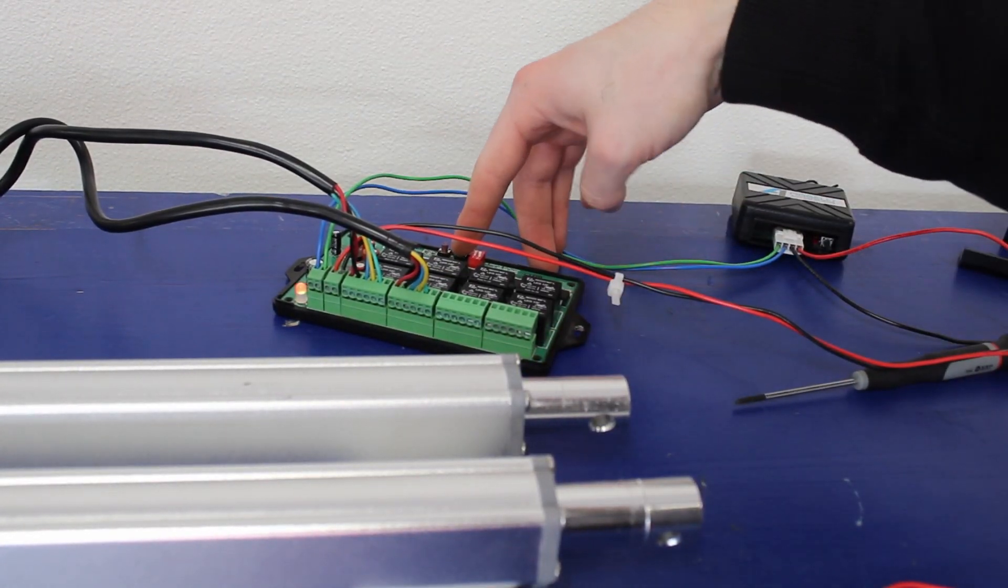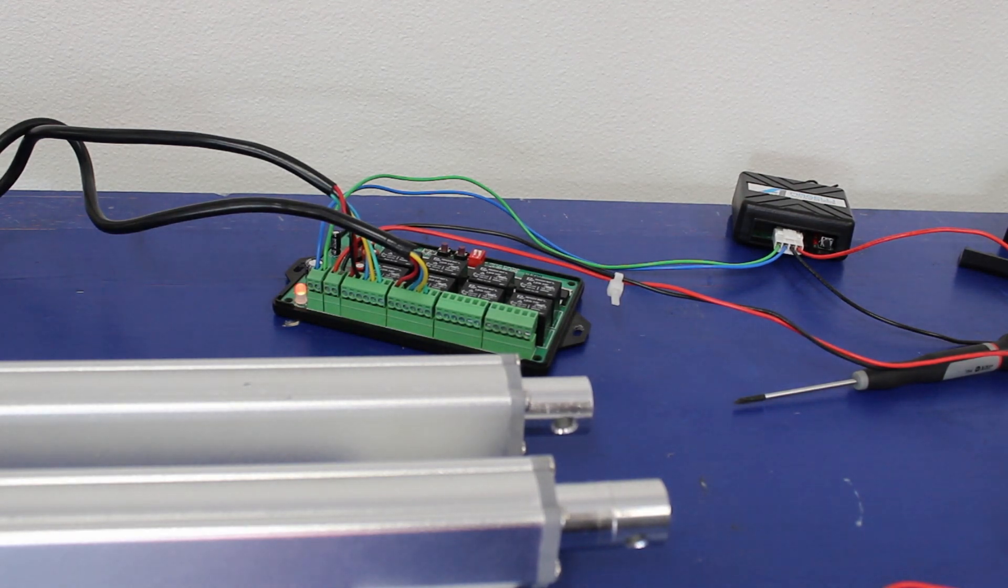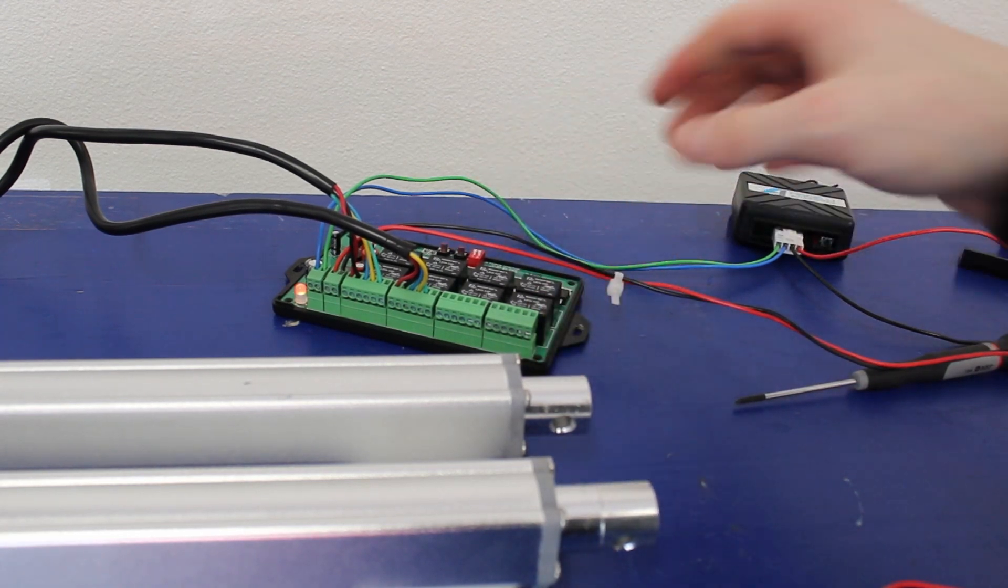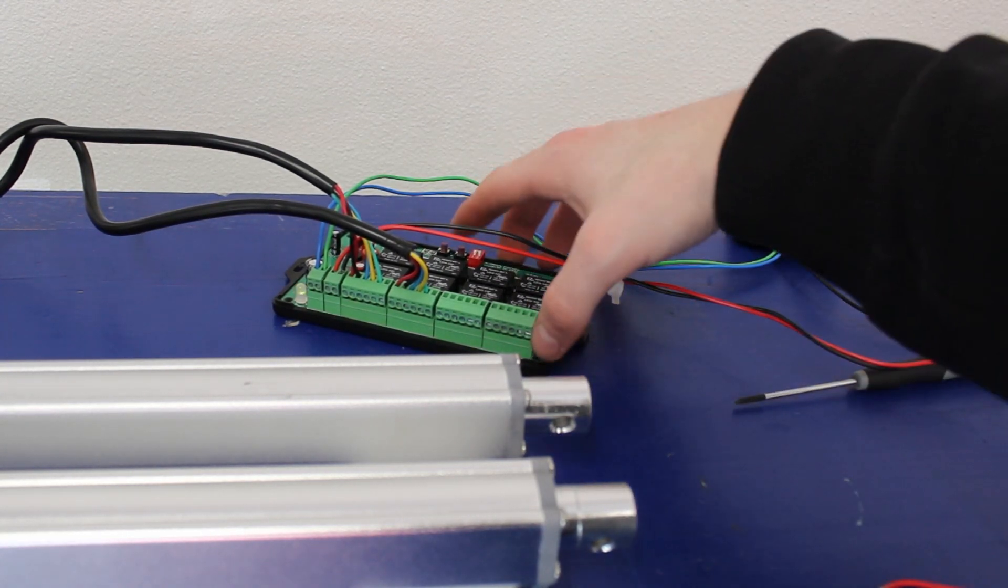Taking off the cover so you can see, we're going to send it back to home. And now, oh, that one didn't retract all the way. All right, that is telling me more information. It turns out that one is actually our bad actuator. I just did not know it at this point.